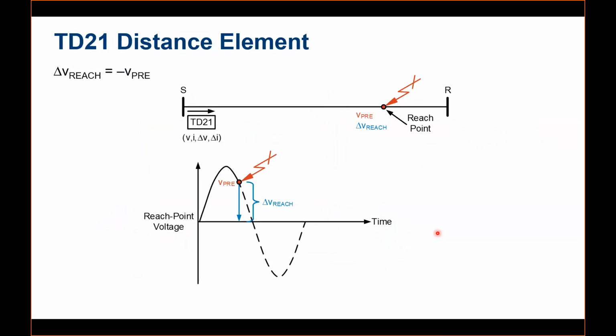Next is a distance element, which is based on incremental quantities. To understand the distance element, we will consider that there's a fault at the reach point, because this is an underreaching zone. It's not 100%, maybe set at 70% or 80% of the line, similar to the instantaneous zone that we set in a distance element. At the reach point, if you consider a fault here, somewhere on the waveform, whenever this fault happens, and considering this as a voltage fault, there is a pre-fault voltage, and it will die down, or go to zero, immediately with a change in the voltage. We call this the reach voltage.